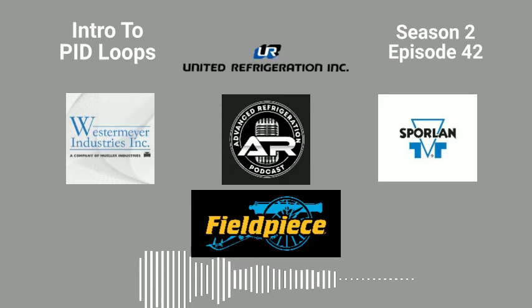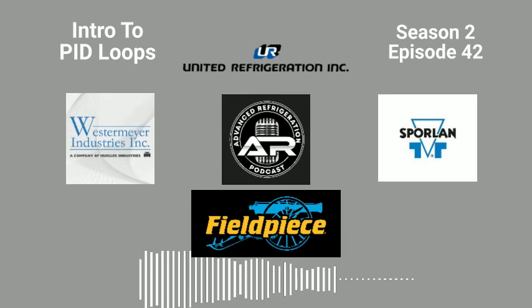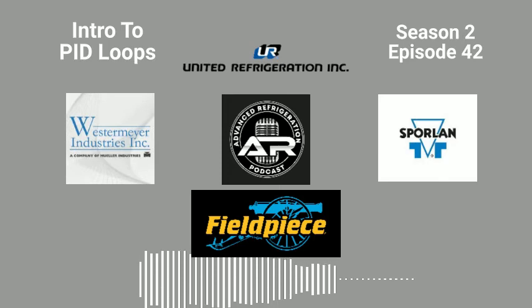Okay, so we're going to go over proportional first. Proportional is a value which gets added every single time the control value is away from set point. So it's proportional, it moves with it. Say a valve is trying to maintain a 20-degree set point, and your PI loop is set to 2. It's going to multiply by 2 every time it gets above set point.